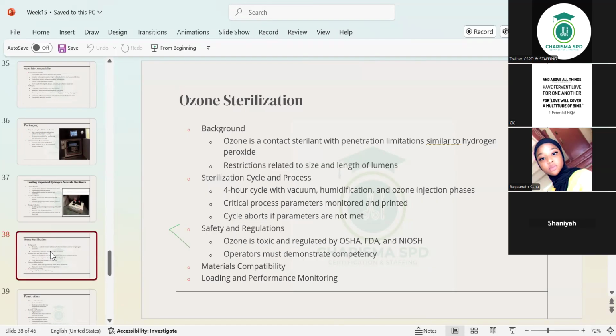4 hours. Okay, you're going to work for 8 hours, which means that if you start as soon as you go in, if you push in a load for ozone, the only thing you can do is just one load per day. Because after 4 hours, it has to cool down. There should be aeration before it comes out. Then you can push in the second load. Because who is going to take the second load out when you are out of the place? Okay? So maybe that's why I don't like it, but I don't know. It just doesn't appeal to me. But it has its good side, as I said. If it's the best for your situation, you've got no choice but to use it and get used to it.